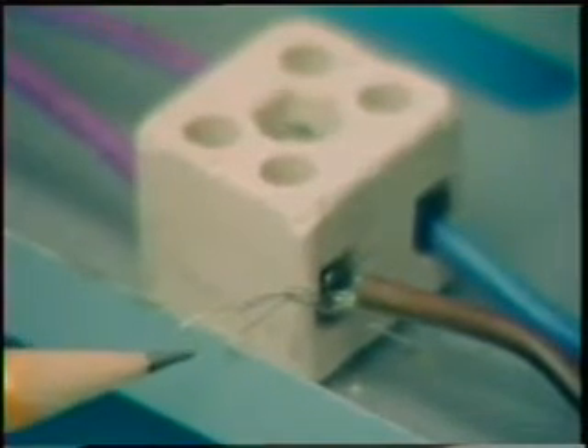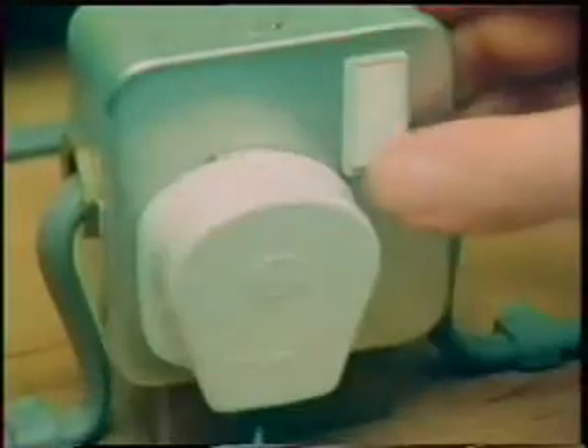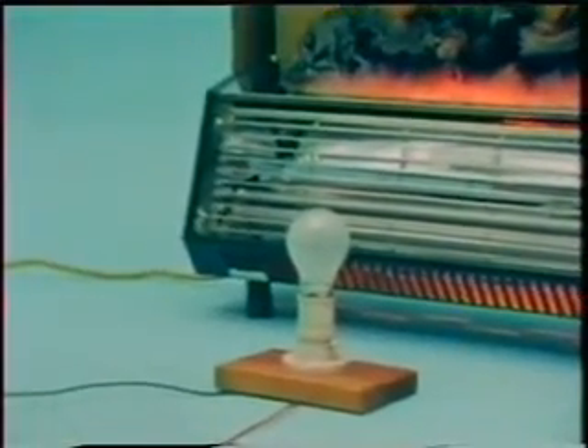But using the correct fuses won't help you if you make other connections wrongly. We're going to wire up an electric fire deliberately, very carelessly — this isn't one for you to try for yourself. Did you notice that straggly bit of wire sticking out? When we connect this, the live wire, to the junction box, that strand is left touching the body of the fire. And the earth lead — green here, as on some older cable, but green and yellow on modern cable — hasn't been connected to the earth connection on the fire. The fire works perfectly well, but all the metal work is live because of that stray bit of live wire touching it. You'd get a severe electrical shock and perhaps a terrible burn if you touched any part of the fire.